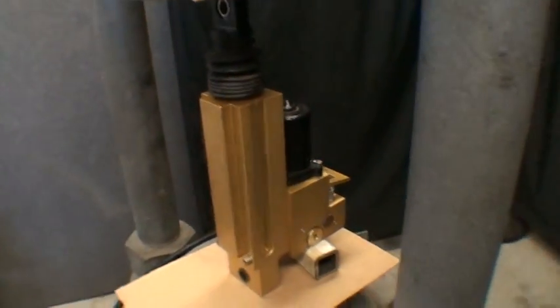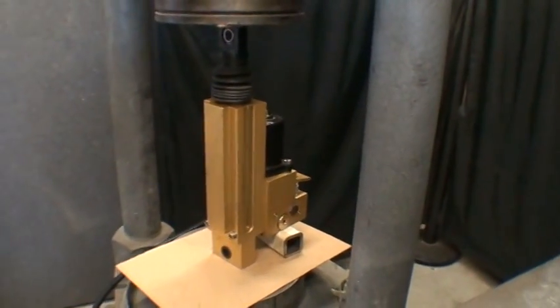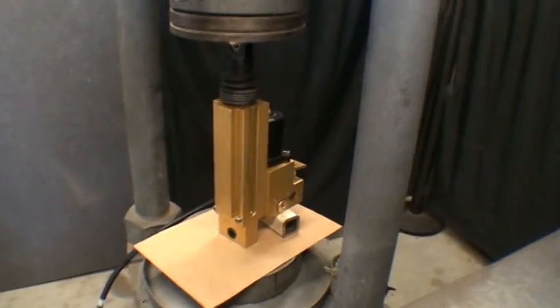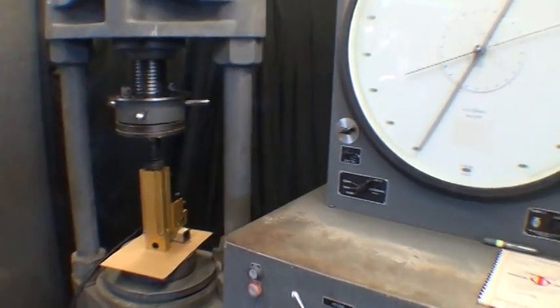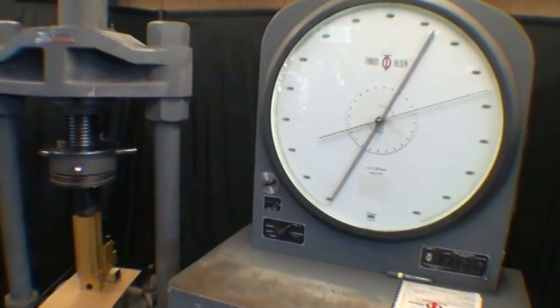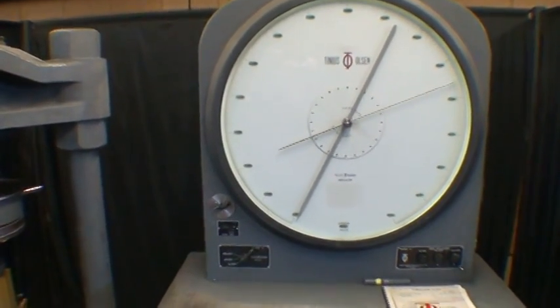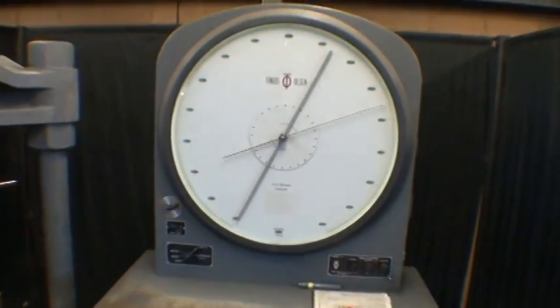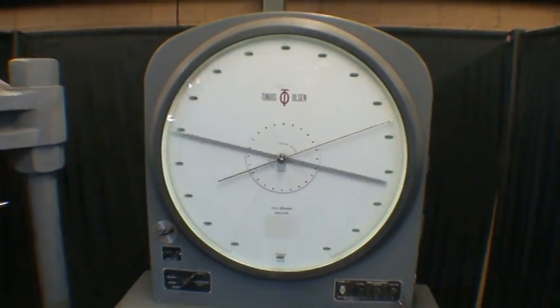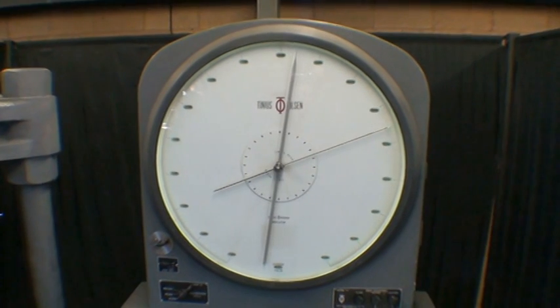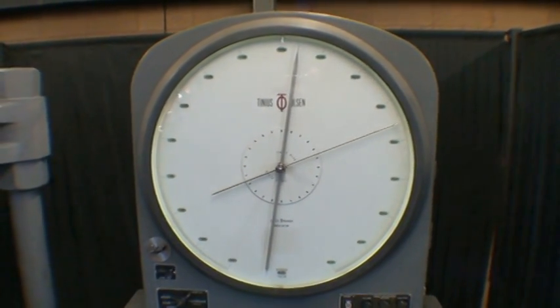This then raises and lowers the actuator rod. We just have it in a load frame to determine the force of the actuator because the actual specs aren't known. So we'll put 24 volts to it and see that it makes right around 8,500 pounds.